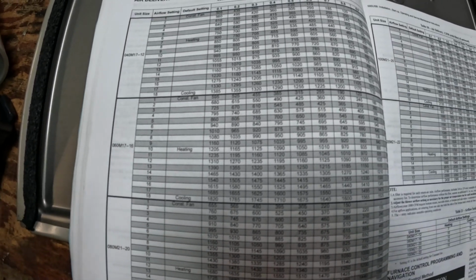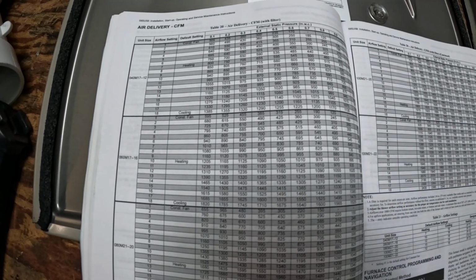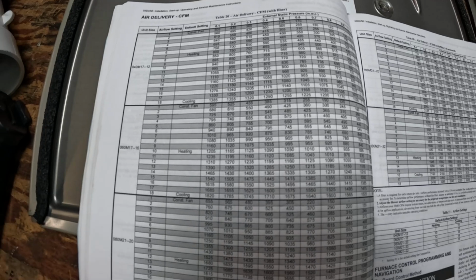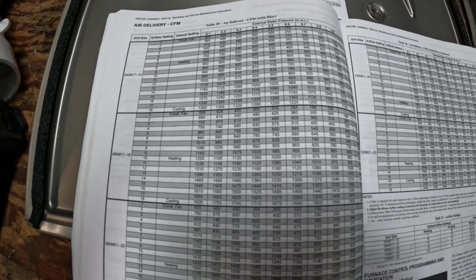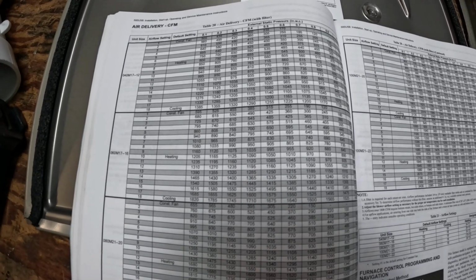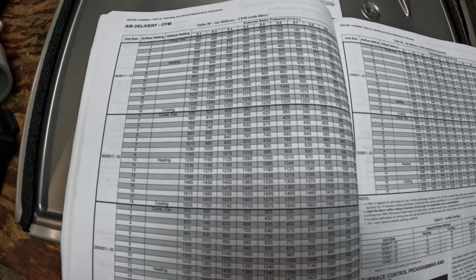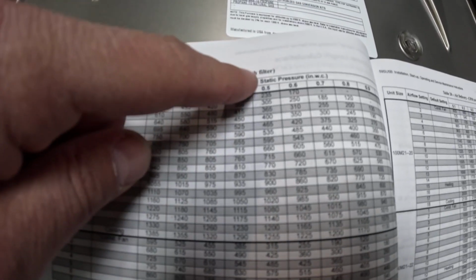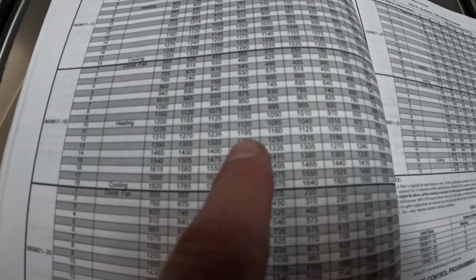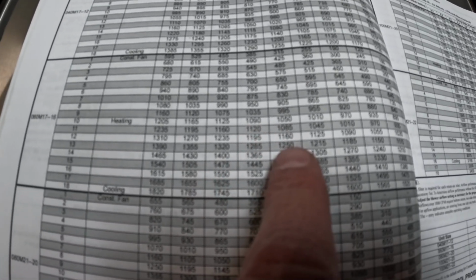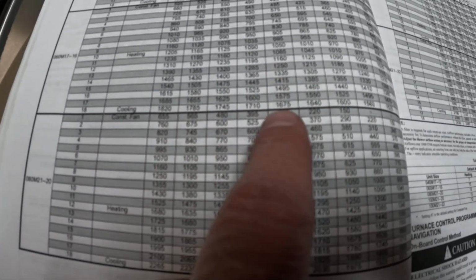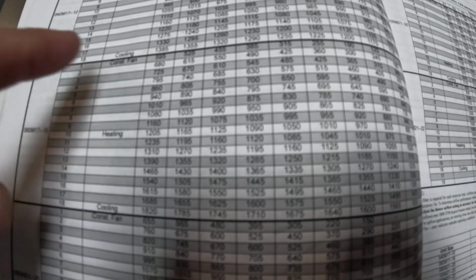What you need to do before you even program this is know your ductwork size. On this system, let's say it's a perfect 4-ton system, 400 CFMs per ton at 0.5 static. So we're going to look at the 0.5 static pressure. We're going to come down, and on heating, we're probably going to set it for around an 11 or a 12. And on cooling, we're probably going to go at a 17, which would be 1575 CFM. Your constant fan, you're probably going to move up around 11 or 12 as well.